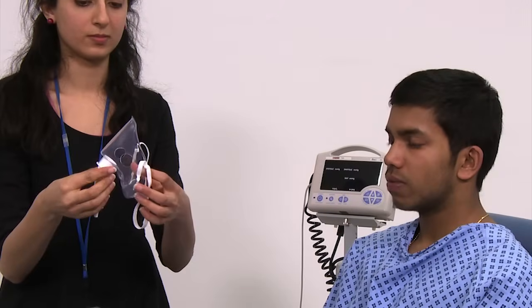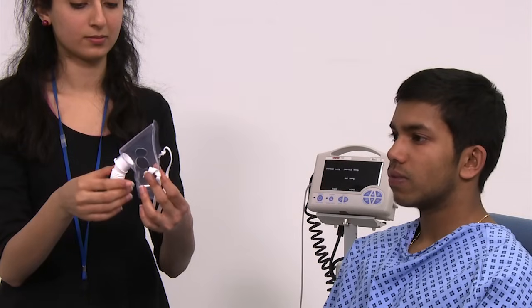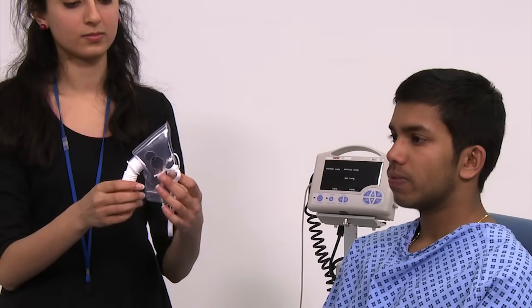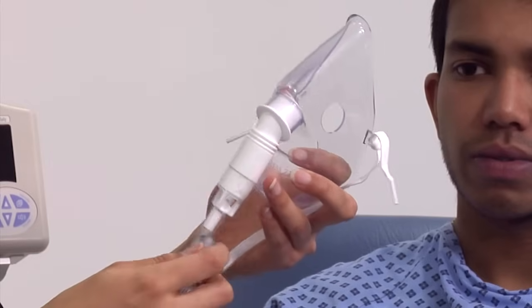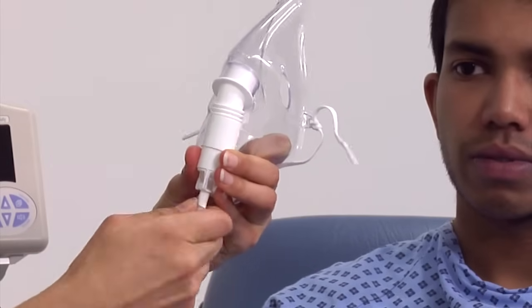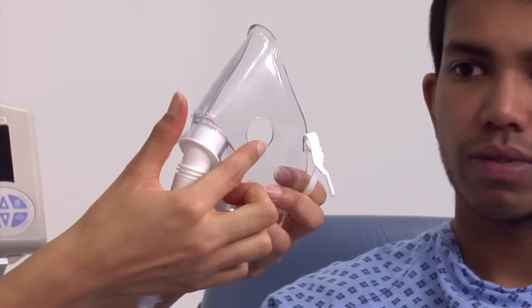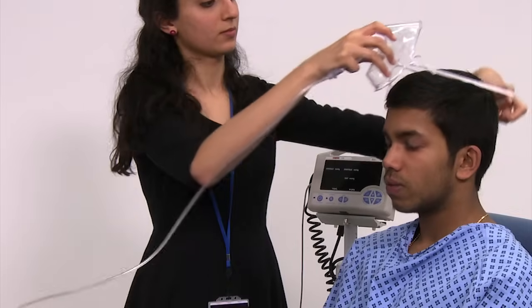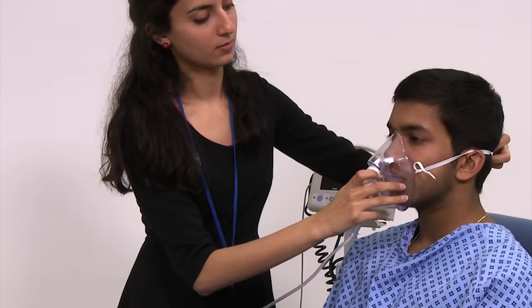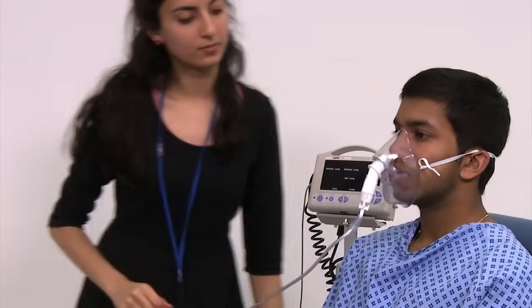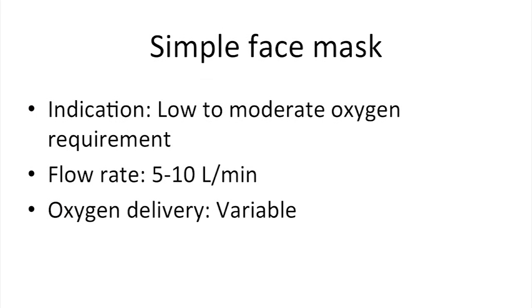An alternative to nasal cannulae is to use a simple face mask. This is less comfortable for the patient, but can deliver slightly higher concentrations of oxygen. The oxygen tubing is connected to the plastic port at the bottom of the mask. The open side ports allow air to mix and dilute the oxygen, as well as allowing carbon dioxide to leave. The mask can then be moulded to fit over the patient's nose and mouth and is secured by an elastic band at the back. The flow rate should be adjusted to between 5 and 10 litres per minute. However, it is difficult to know exactly how much oxygen is being delivered through a simple face mask.